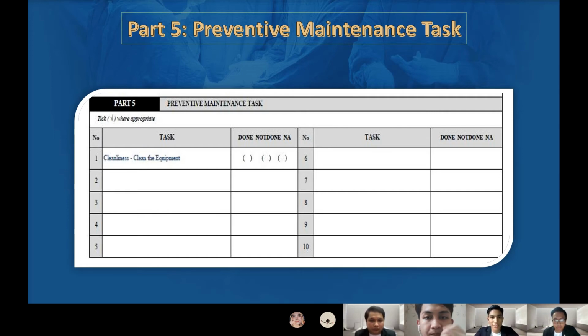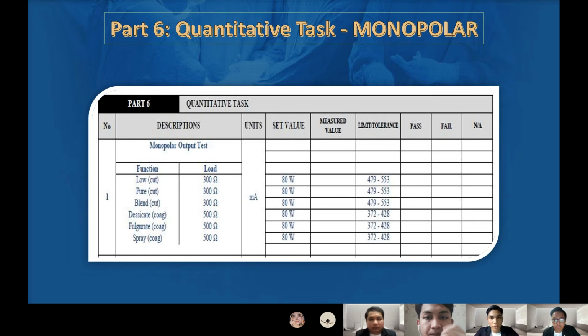Part 6 is quantitative tasks. For the quantitative tasks, we have two: the monopolar output test and the bipolar output test. What is the monopolar output test? In monopolar mode, electrical current is delivered to the patient via an active cable and electrode, and the current returns to the unit through a return electrode pad or plate, which splits and returns the current, thus preventing focused heat, which can cause burns.